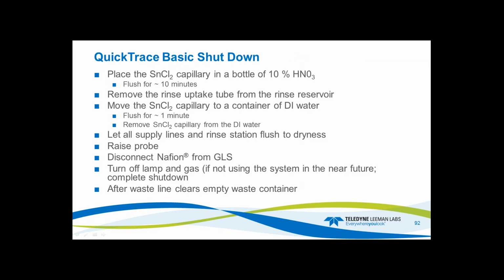So some of the shutdown. So what do we do to shut this system down? It takes like 5 minutes, 10 minutes max. Place the stannous capillary in a bottle of nitric acid, 10%, 10-minute rinse. Remove the rinse uptake from the rinse reservoir at that point, and then move the stannous to a DI water. Rinse that out, flush for a minute. Remove the capillary from the DI water.